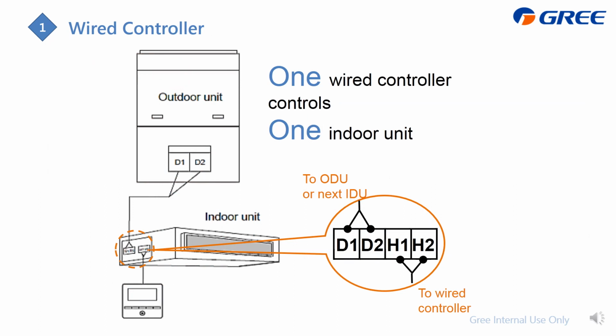As for how to do the wiring, it's very easy. On the indoor unit, here are the terminals. D1, D2 is for the outdoor unit or the next indoor unit. For this wire controller, you just need to connect to H1, H2. This is one wire controller controlling one indoor unit.